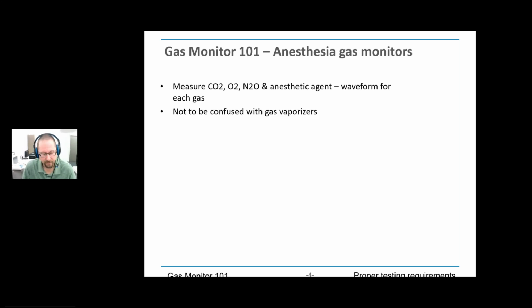Now, I want to be sure that you realize we're talking about gas monitors and not gas vaporizers. Gas vaporizers are the devices on the anesthetic bench that you put the liquid anesthetic agent in, and it vaporizes that agent into a gas, and then the patient inhales it. We're talking about the other end of it, where the monitor is then sampling the breath they exhale and analyzing what's in that sample to determine how much CO2, O2, or anesthetic agent is actually in their breath. So that's the device we're talking about, the monitor side of it, where it's sampling.